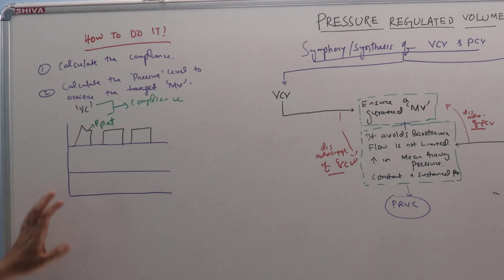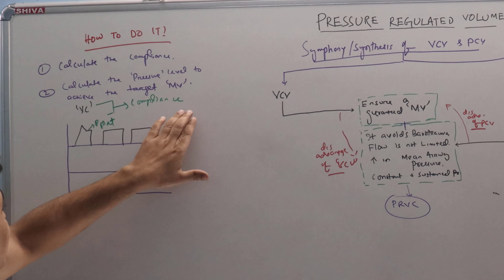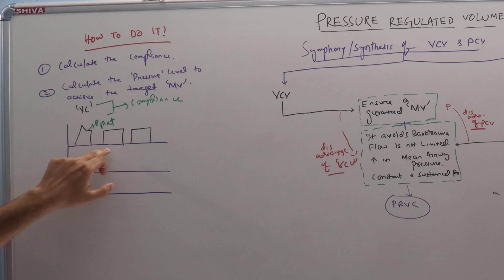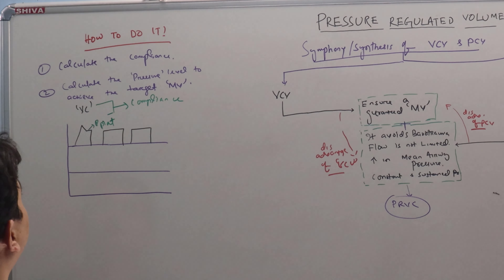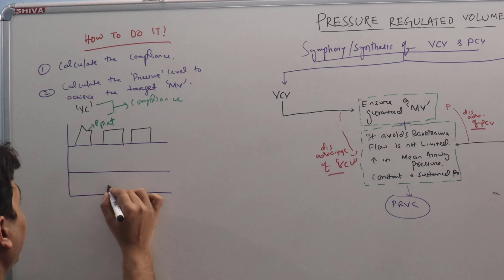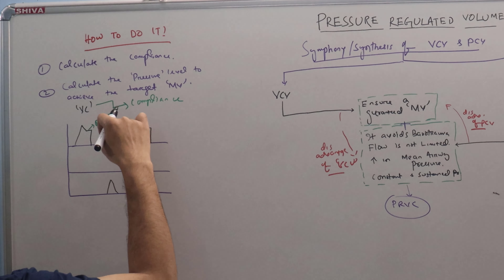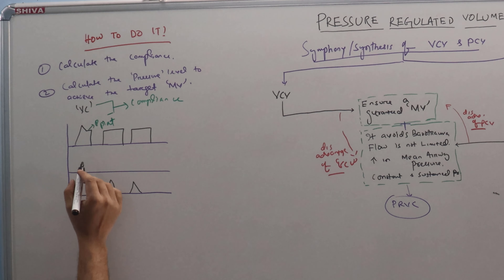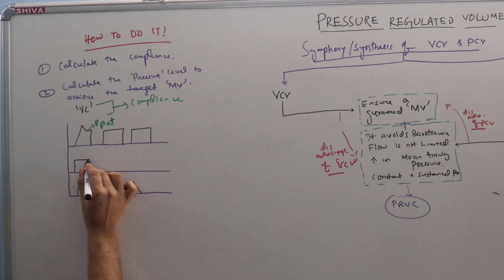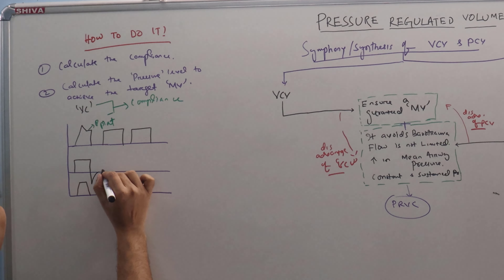The first breath will be a volume control breath, and from this VC breath we will find the P-plateau. Using both these factors we will find out the compliance. Based on this compliance the ventilator will calculate the inspiratory pressure level to achieve our desired ventilation. From the next breath it will be a pressure controlled breath. The ventilator may take 1 to 3 breaths to decide the appropriate compliance of the lung, and based on that the pressure control level will be selected. This pressure control can be high or low depending upon the respiratory system compliance variation from breath to breath, so the tidal volume will also be different.